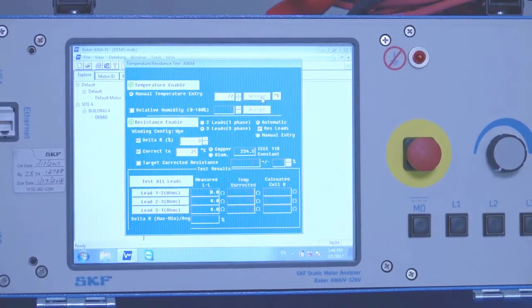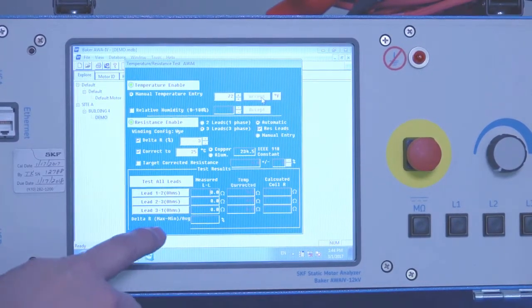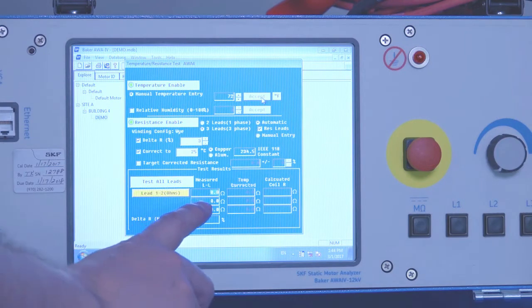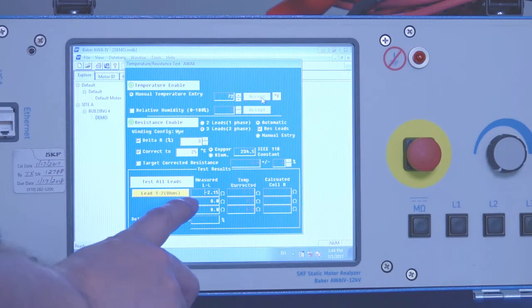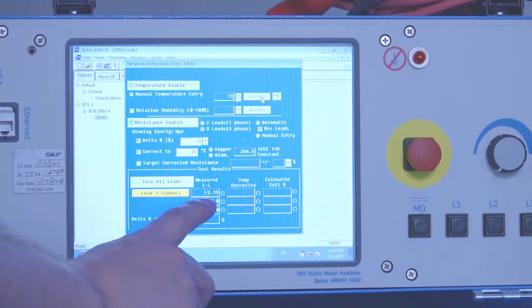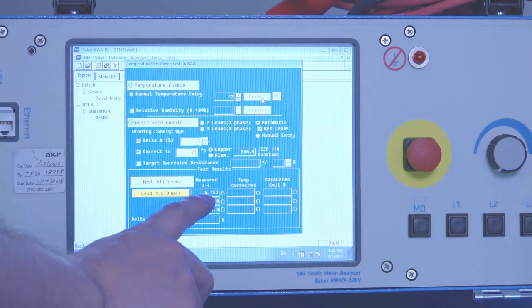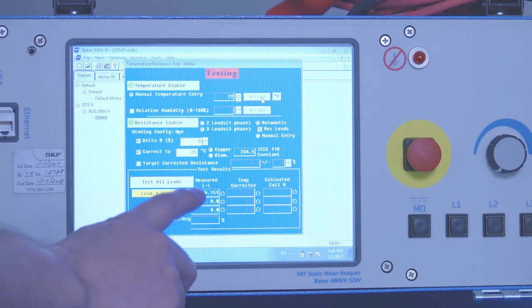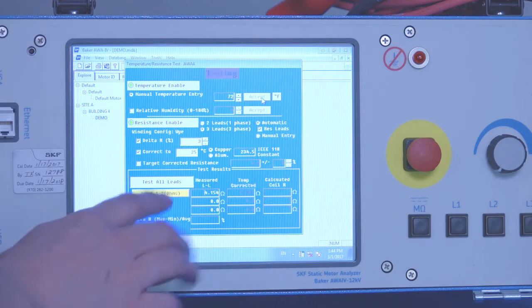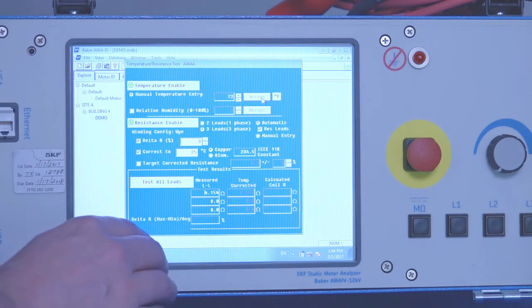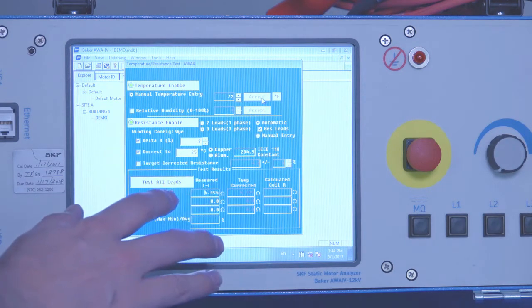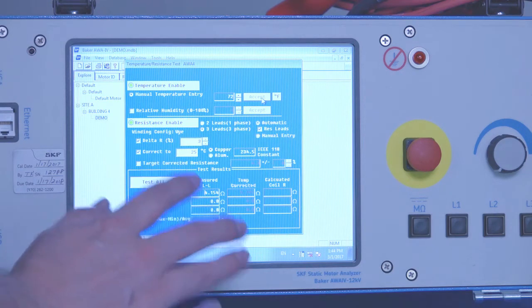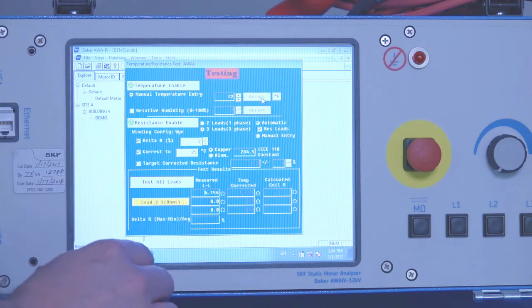And that will initiate the low voltage resistance measurement. And we'll see the resistance values start to populate here. It should settle fairly quickly. If it oscillates during the test, there may be indications of induced voltage or rotating rotor.